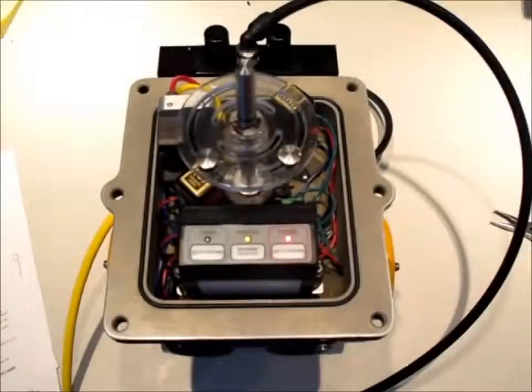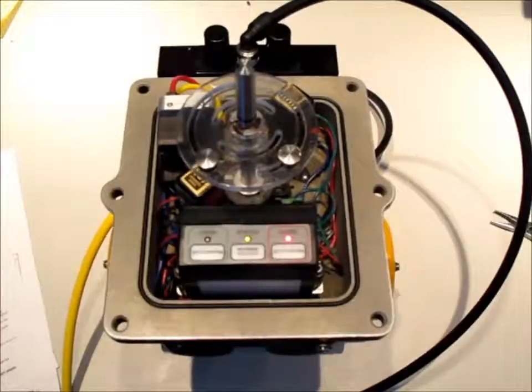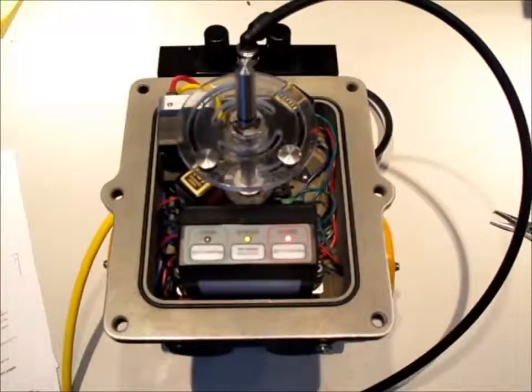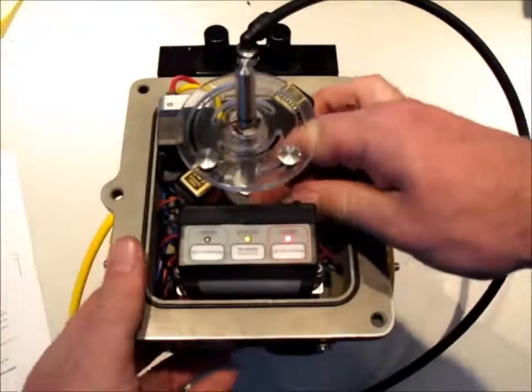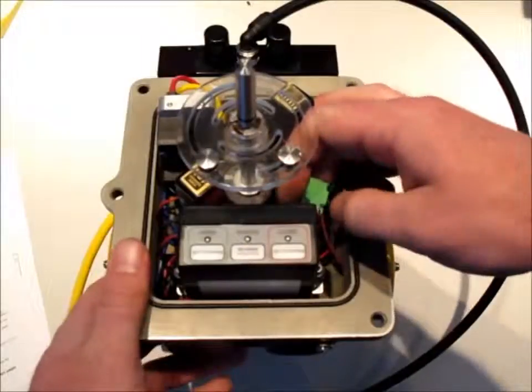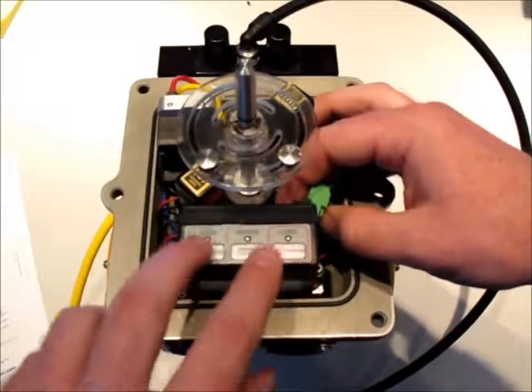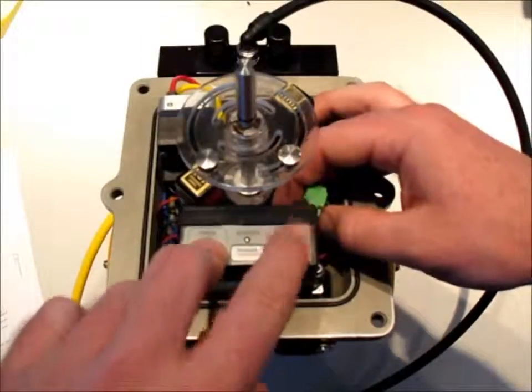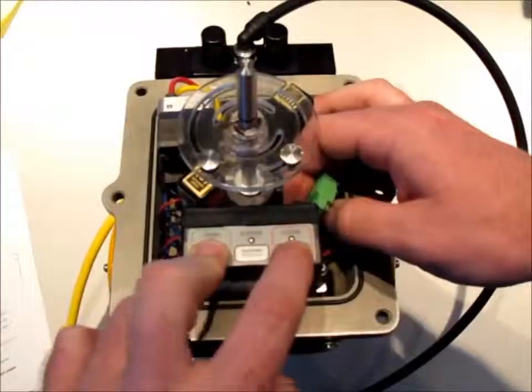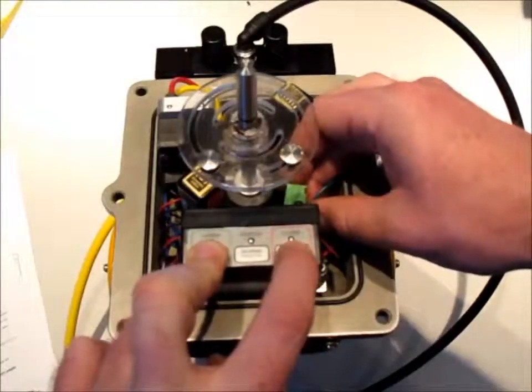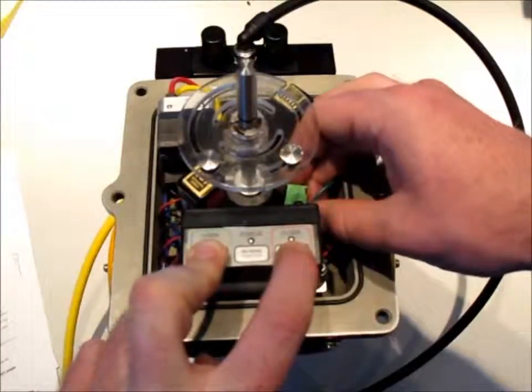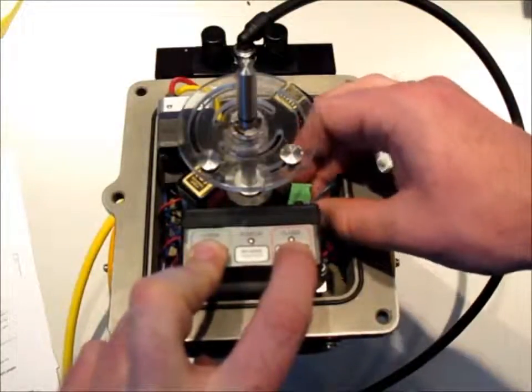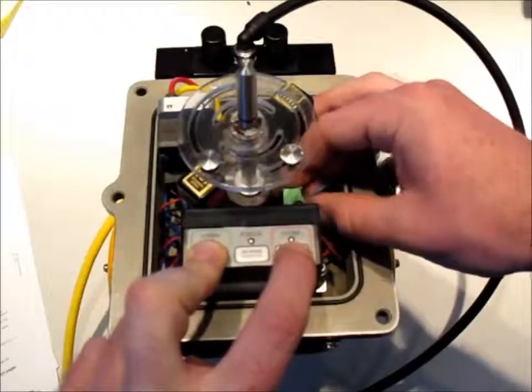To restore factory defaults locally, remove power from the cube. Now, before restoring power to the cube, press and hold the set confirm button for both the open and closed side.